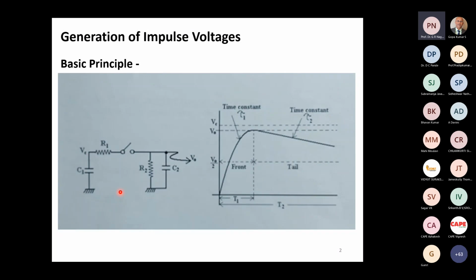Now, how do we generate this voltage? I'll go through only the principles because the main purpose of the webinar is in the other directions we have already been discussing. Here, essentially, what the test facility is capable of is the main point under discussion. Now, what we do is we have a huge transformer and a huge capacitor, charged to the required voltage, and then it discharges when commanded. When the switch closes, it discharges through a parallel combination of a capacitance and resistance. So I have C1, R1, which we call the discharge resistance, R2 is the time to tail resistance, and C2. The front time is dictated by R1 and C2, R1 and C2.